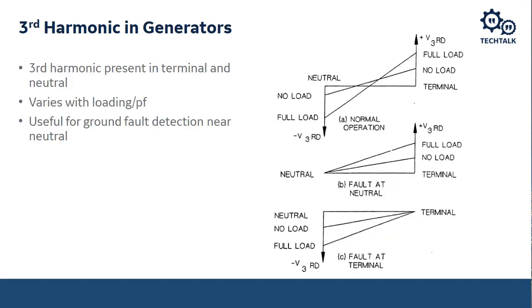The third harmonic. Third harmonic is generated in a generator when it's running. There's always some third harmonic current and voltage present at the terminal and the neutral, and the distribution of third harmonic is pretty linear from the neutral up to the generator terminal. We can use that to detect a fault, because if there's a ground fault, the neutral voltage will, if the fault is at the terminal, drop to 0 from a high positive number. If it's a fault on the neutral, it will drop to 0 from a high negative number. So we can use an undervoltage third harmonic, or 27TN, element to detect ground faults within the generator.